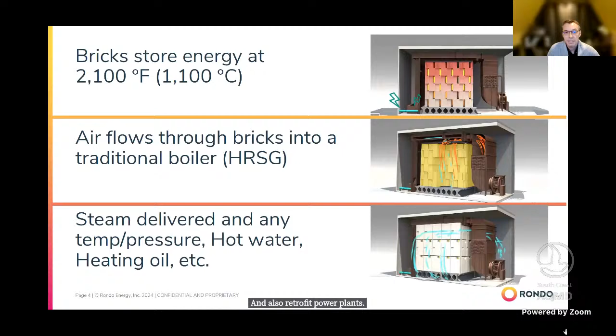Next slide. So a lot of the early questions we always get from industry is, well, are you commercial? So the system on the left has been operating in California for the last 18 months and is in commercial operation today. It is a full-scale, full technology demonstration, but it's also kind of a baby heat battery. The one on the right is coming online here in 2025. And that 100 megawatt hour unit, most folks in the industry don't really think in energy storage terms, but that system replaces a 24 million BTU per hour gas boiler. So our heat batteries are really being built for the size of industry. And that's like our smallest model. So we really are designing for industrial heat sizes. Some of the other folks talked about it, but the industrial heat space, oftentimes the thermal demand is 10 times bigger than the power demand.